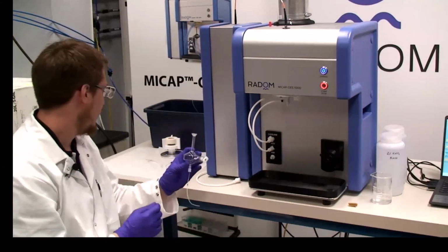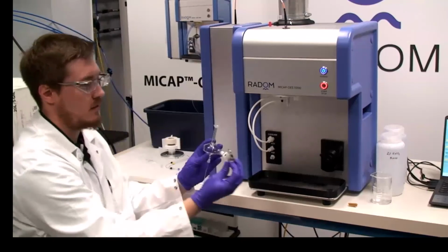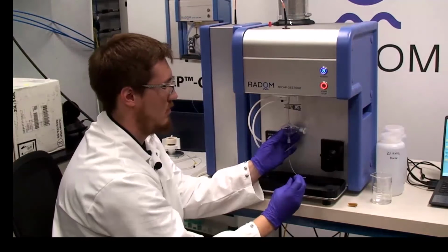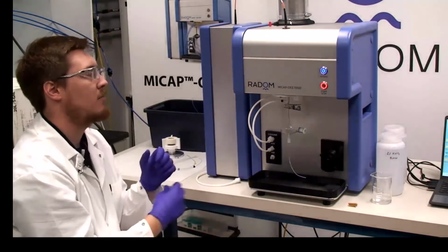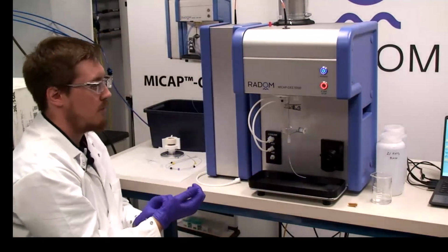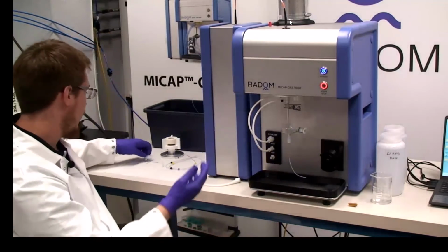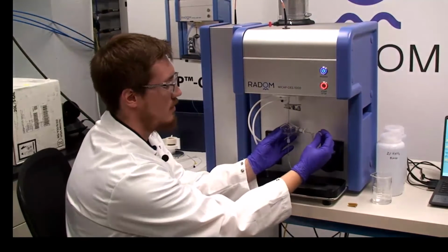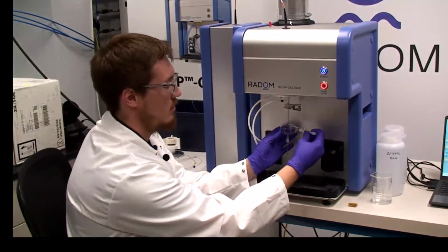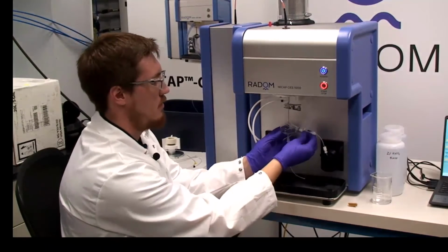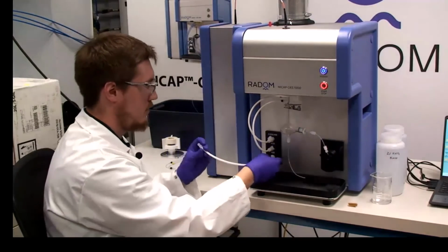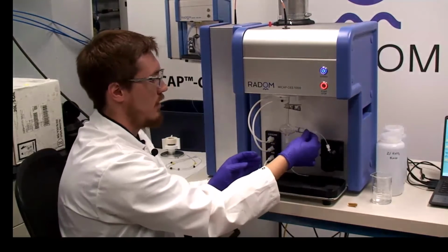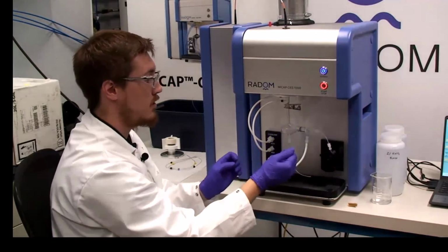Next, we will be assembling our spray chamber. There is a clamp here that hooks on like so, and the spray chamber is responsible for filtering the droplets of spray from the nebulizer to get a finer solution up into the torch. Next, we have our nebulizer, and it just slides into the spray chamber. The nebulizer will use the nebulizer gas and combine that with our sample to create an aerosol, which is injected into the spray chamber.